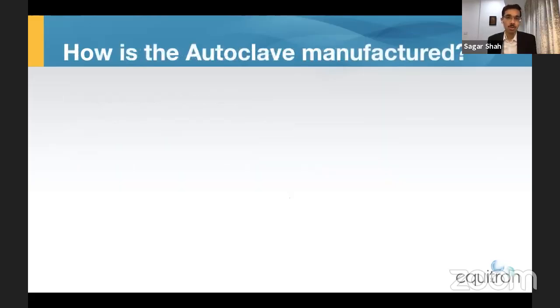Knowing the answer to this question as to how your autoclave is manufactured is of utmost importance, because if you want to keep your lab environment safe, and if you want to know whether your investment is truly worth its value, the answer to this question forms the crux of it. At the outset, an autoclave is a pressure vessel that is expected to last over many years. So when you invest in an autoclave, it is an investment not only for a decade or longer, but much more. Typically, autoclaves are not recommended to be used beyond 10 years if they're not validated, but we do see customers that are using autoclaves for a much longer time without validation. So that's something that you would need to look at.